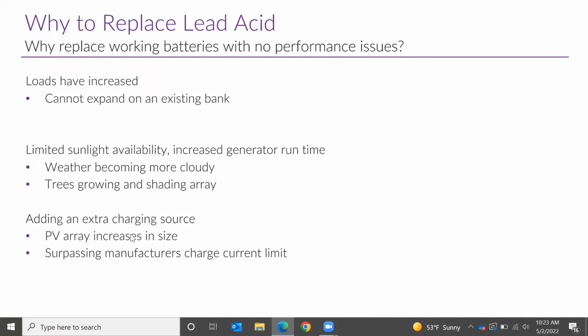Going along with that same thread, if you need to charge your battery bank faster—maybe you're adding a PV array, another string to your array, or a wind or hydro system—if this is going to cause you to increase the charge current beyond the manufacturer's limit, you're going to need to look into a different battery type.